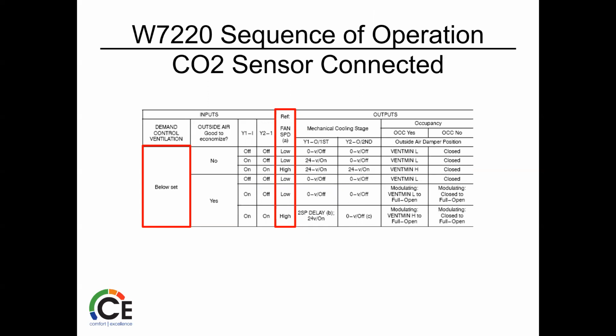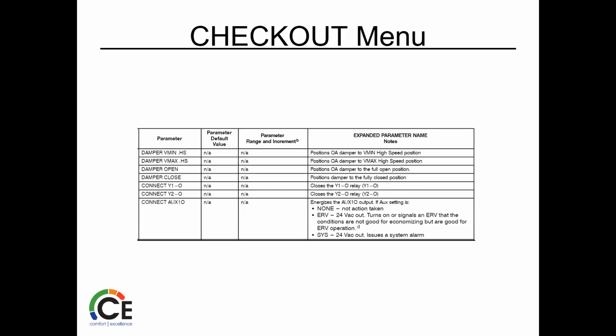If we're doing that, then again, CO2 sensors connected to the W7220, the control will automatically self-enable the DCV functions. May take an hour to self-enable the first time. Why it's so long, God only knows, but it is. If the space CO2 level is below that set point, the operation sequence looks the same as always. If it's over that, then of course it's going to go into operation mode.